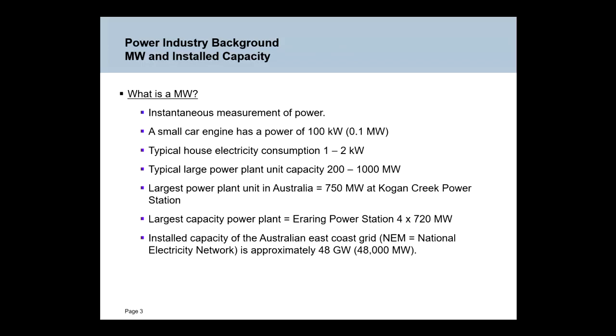Okay, so first things, power industry background. What is a megawatt? I'm sure many of you have done engineering of some sort, and in the power industry we talk about megawatts. A megawatt is an instantaneous measurement of power. To put it in context, a small car engine has a power of around 100 kilowatts, 0.1 of a megawatt. Typical house consumption is 1 to 2 kilowatts. Typical large power plant capacity is in the range of 200 to 1,000 megawatts. A large power station like Kogan Creek, the largest unit is a 750 megawatt unit at Kogan Creek in Queensland. And the largest power station in Australia has 4 720 megawatt units. The installed capacity of the grid on the east coast of Australia is about 48,000 megawatts.